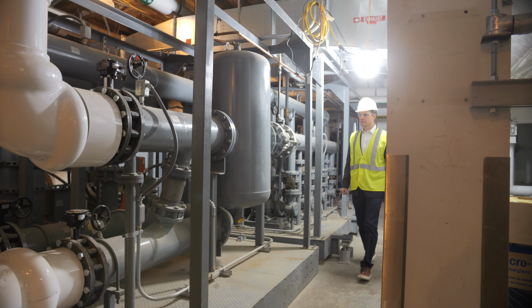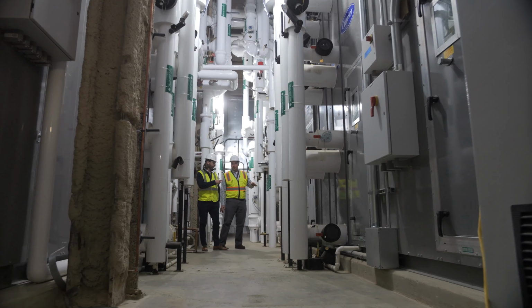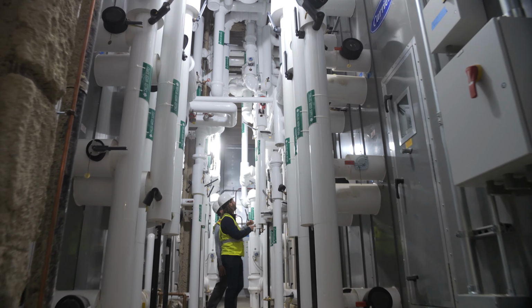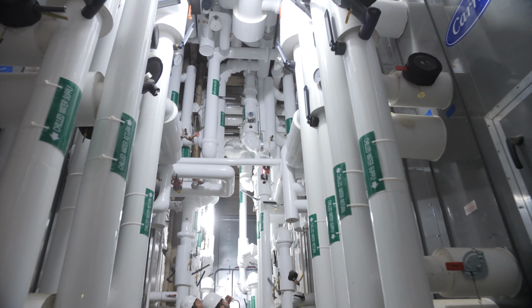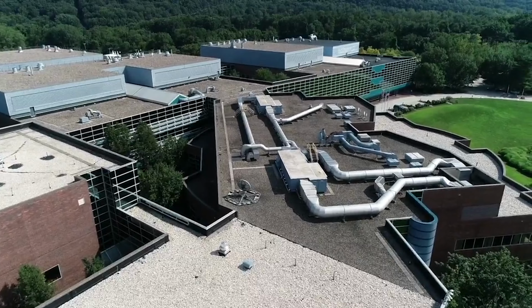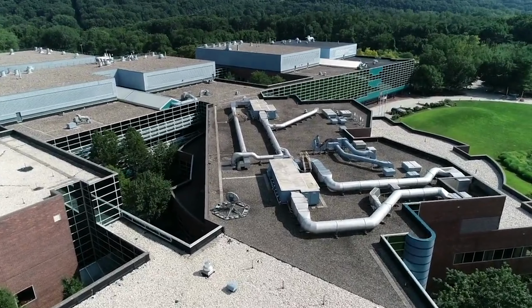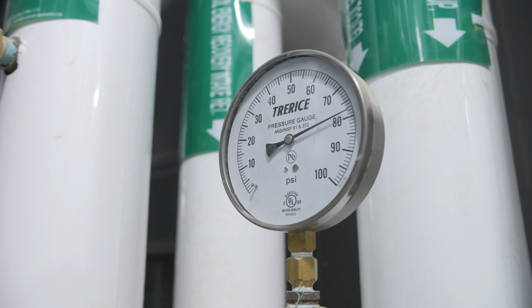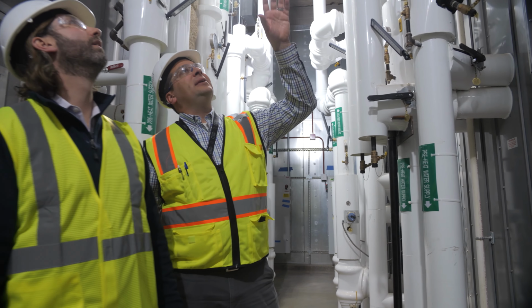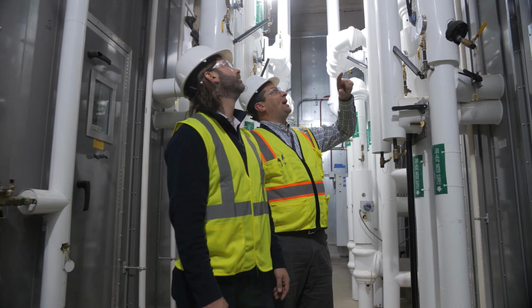The air handling systems that serve these GMP-type labs are always treated with chilled water and steam from the main campus. These large air handling units are moving voluminous amounts of air throughout the building all the time, and it's critical that the air is treated, filtered, and brought to the space at the right temperature and relative humidity tolerance.